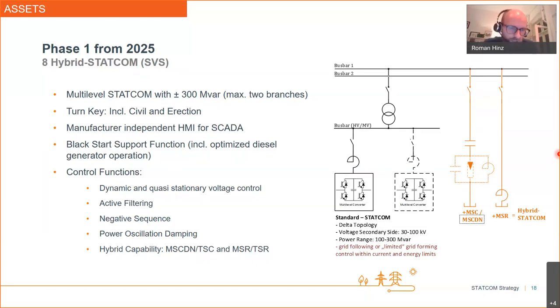via the circuit breaker if the demand for reactive power requires it. This is usually done by a reactive power and voltage linear function. It's usually quite easy. You can select a slope, like a droop, and then the STATCOM will react with the correct reactive power, depending on the set point you set for your voltage. This is what we tender right now. And what is also important for us is a black start support function.